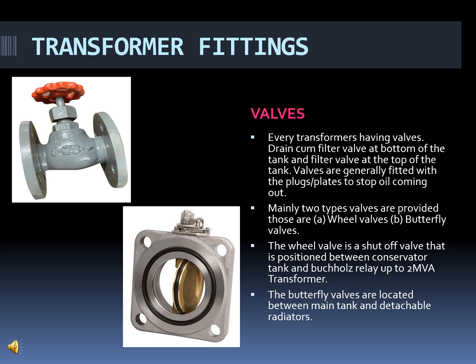Now the fitting number 5 is known as valves. Every transformer has a valve. There are 2 valves present in every transformer, as you can observe. One is a drain cum filter valve, which is located at the bottom of the tank, and another one is a filter valve, which is located at the top of the transformer tank. Valves are generally fitted with plugs or plates to stop oil coming out.